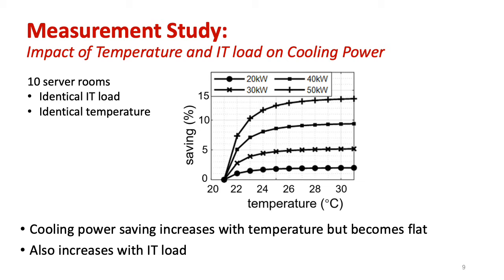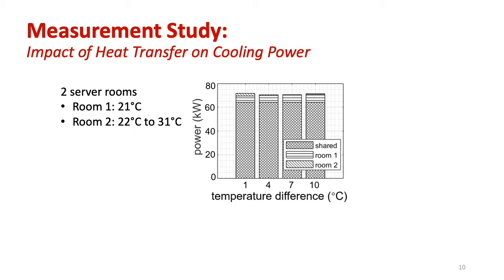We also see that the power saving increases with the IT load. Second, we investigate the impact of heat transfer on cooling power. We simulate 2 server rooms. The first one has a temperature set point of 21 degrees, and we vary the temperature set point for the second server room from 22 degrees to 31 degrees. The figure shows the breakdown of the cooling power versus the temperature difference between the two rooms.